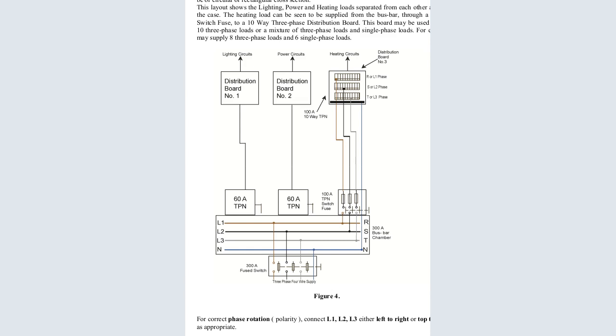This is the fuse for line 1. You can see the live 1 is here. The fuse for line 2 is here. This is our line 2, our next phase. And the fuse for line 3, our next phase, is here, and our neutral is here. And then we have the fuse or the isolator that we talked about. These are the isolator fuses or switches that are going to the distribution board.